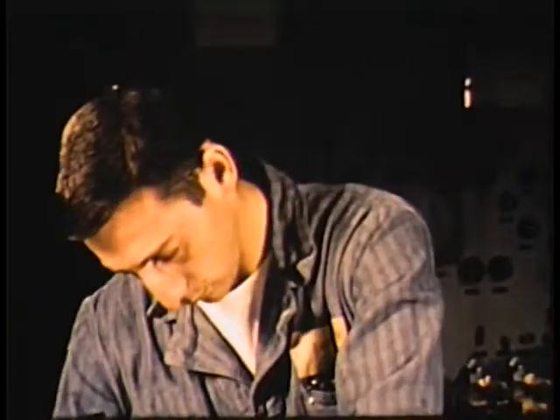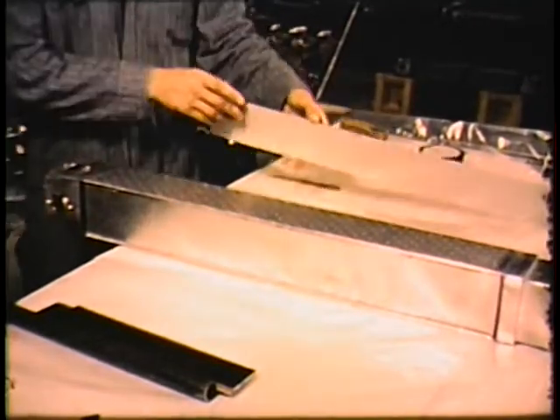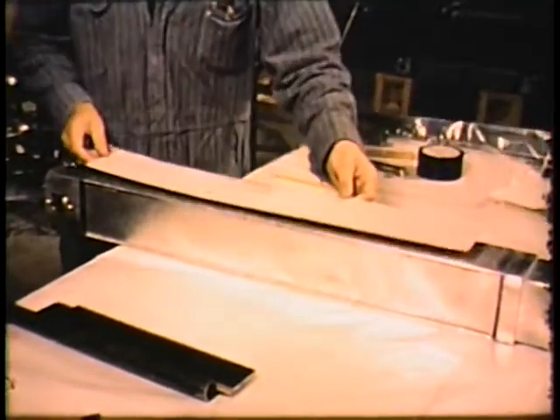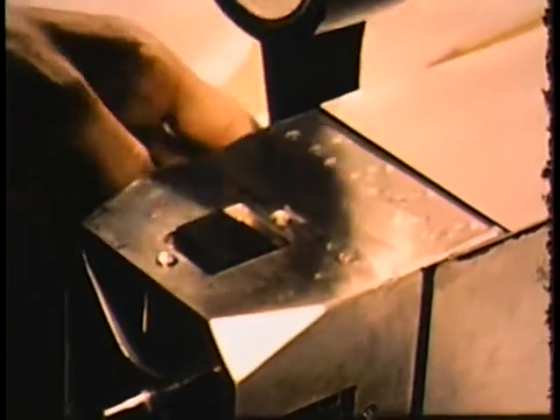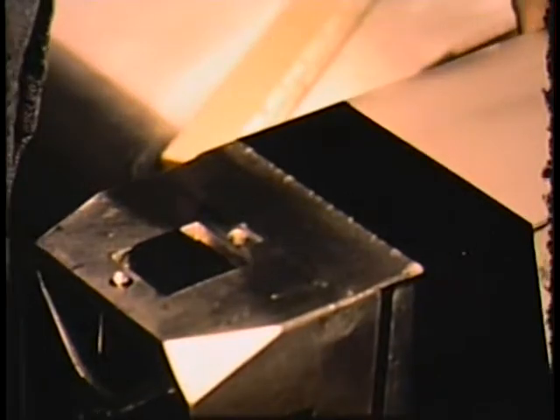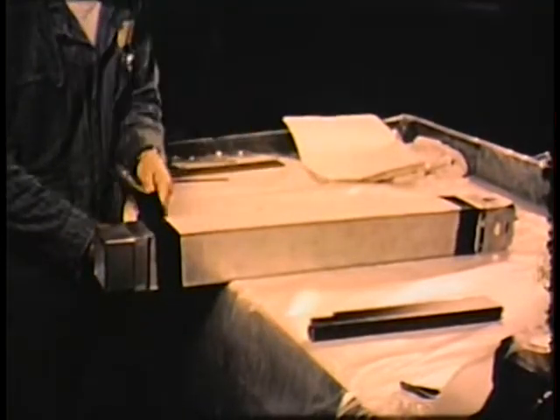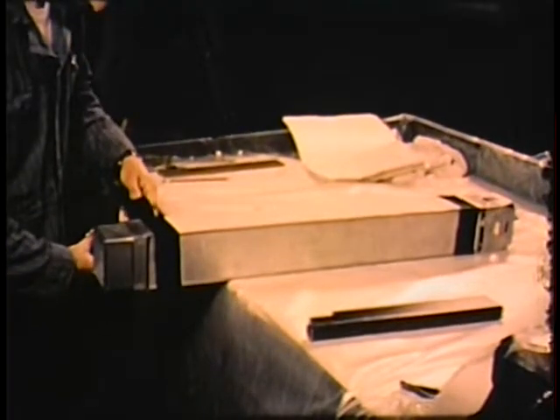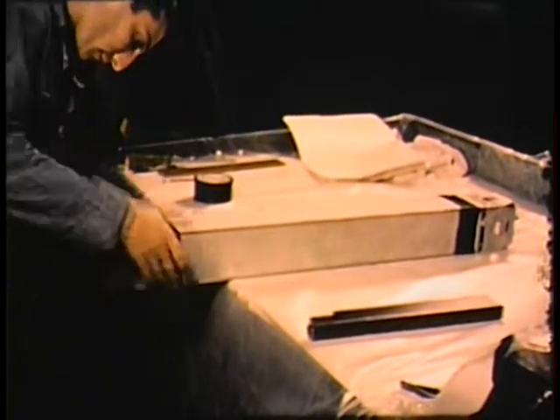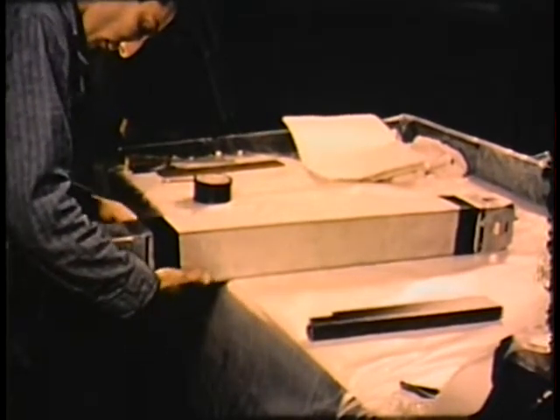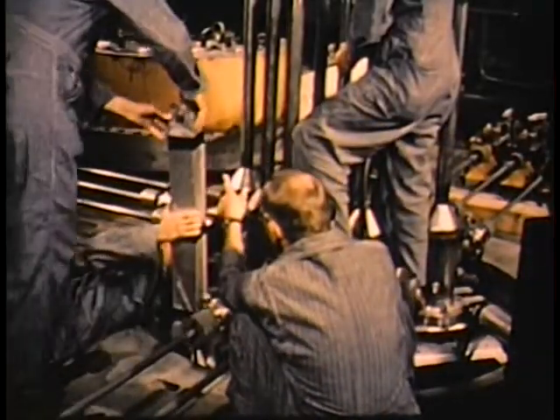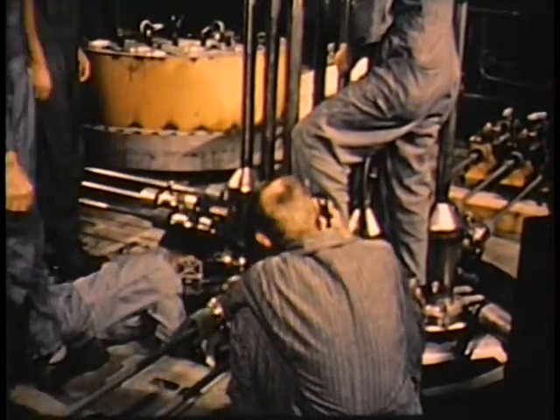The next set of loadings was programmed to terminate with the initial reference core of 40 fuel assemblies, each with one full-length poison strip containing nominally 5/10 of a gram of boron-10 in aluminum nickel. 40 of these strips were available, each strip being 26 mils thick and having the width of one fuel assembly, 3.875 inches, and the length of the active core, 25.8 inches. On August 19, 1958, this first 40 assembly reference core loading, loading number 19, was attained.